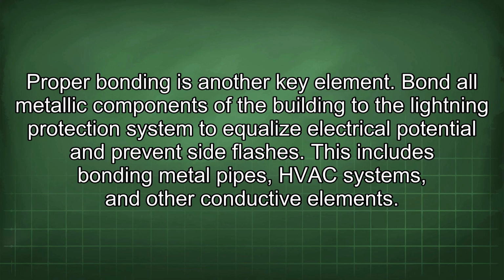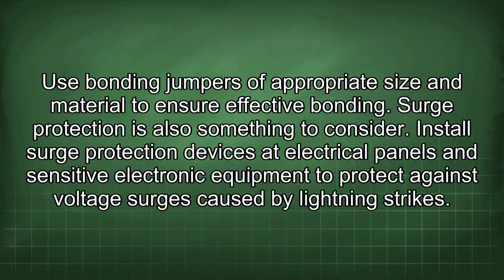Proper bonding is another key element. Bond all metallic components of the building to the lightning protection system to equalize electrical potential and prevent side flashes. This includes bonding metal pipes, HVAC systems, and other conductive elements. Use bonding jumpers of appropriate size and material to ensure effective bonding. Surge protection is also something to consider. Install surge protection devices at electrical panels and sensitive electronic equipment to protect against voltage surges caused by lightning strikes.